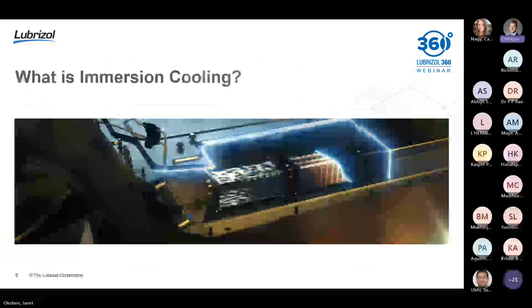we can talk a little bit about the formulations, right? So I mentioned those four parameters: your viscosity, specific heat capacity, thermal conductivity, and density. Of those four parameters, viscosity is by far the biggest lever that we have to pull in terms of optimizing the thermal transfer coefficients for these fluids, where the lower the viscosity, the more efficient the fluid is going to be at removing heat from a system.